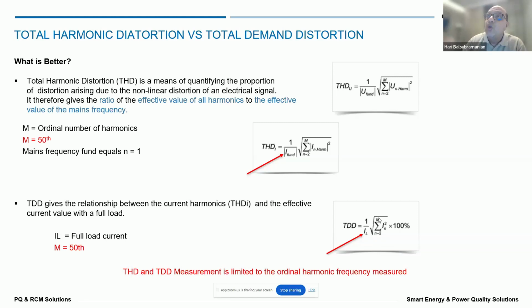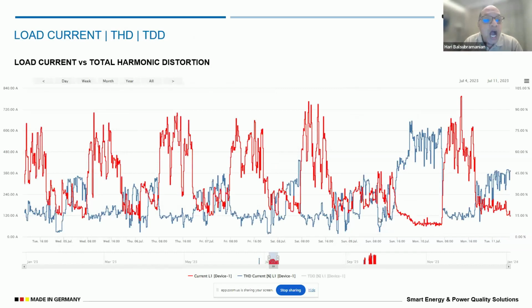Say, for example, so that you know this is your average load and what kind of harmonic you are generating based on your loading factor rather than on the fundamental, where it can be either low or high. I will also show you a simple screen here of how a load current with a total harmonic distortion, THD, is shown here. The red graph is the load current, and THD is the blue one.